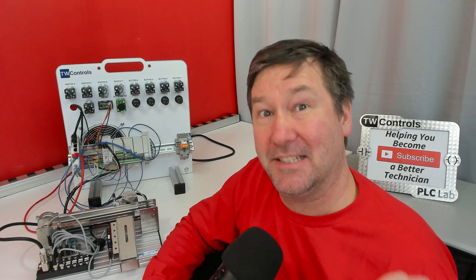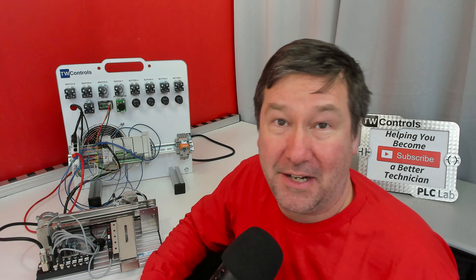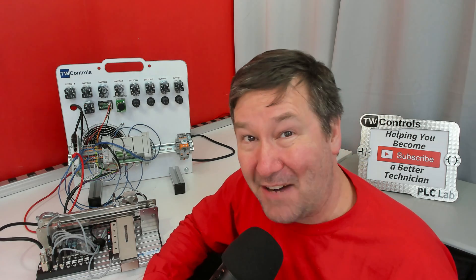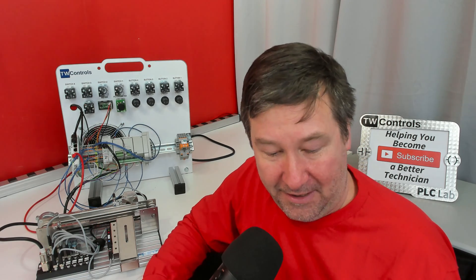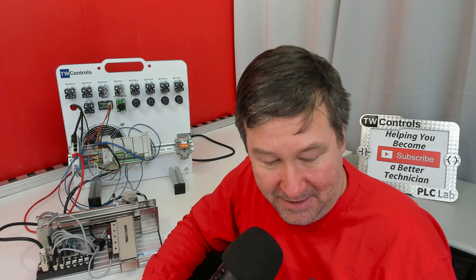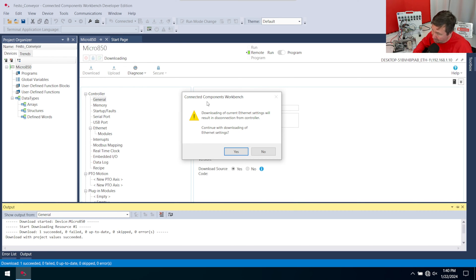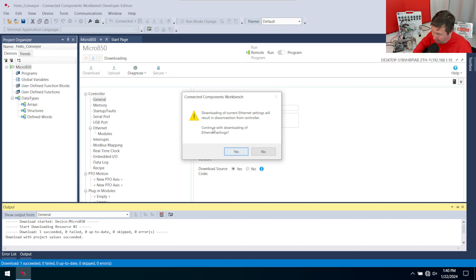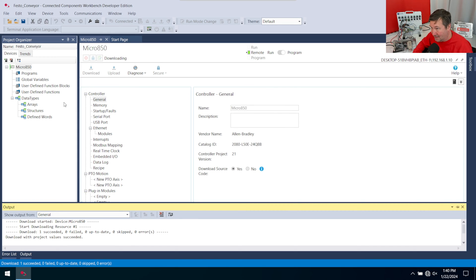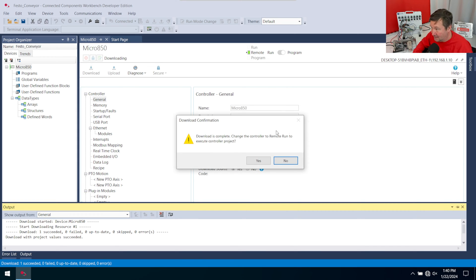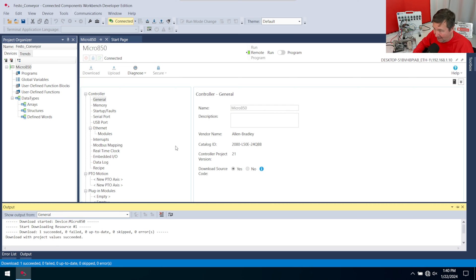And this one is incredibly important with all the micro 800 PLCs. I forgot to set the IP address. Now, we have videos talking how to get through this. But since we've ran into it, it says downloading of current Ethernet settings will result in disconnection from controller. Continue downloading with Ethernet settings. This is the most important prompt to read that most of you will not read because you're waiting to put this in run mode. And normally, this will say we're putting it in run mode. And you just hit the yes, and you lose your Ethernet settings. So we're going to click no to this one. And now it's going to ask us if we want to put it in run mode. But notice it just pops up exactly the same. We're so casually hitting the yes button. We're going to hit yes to that one.